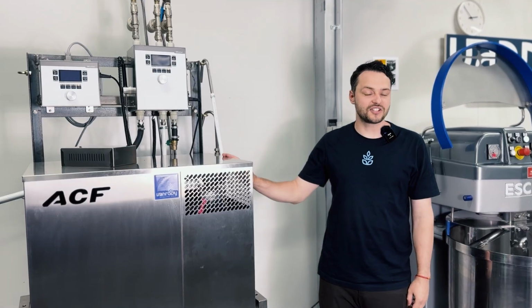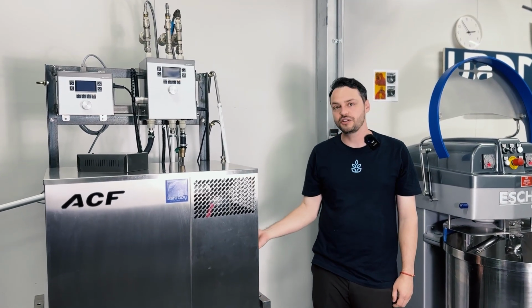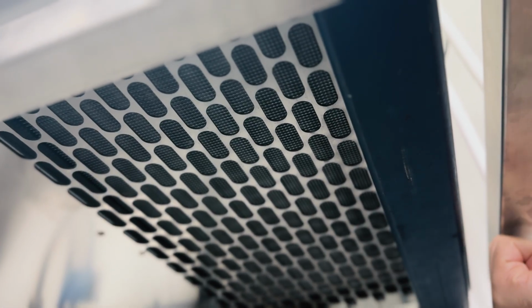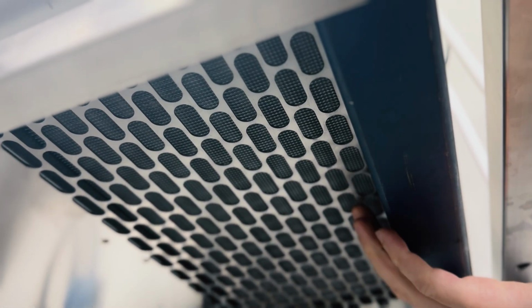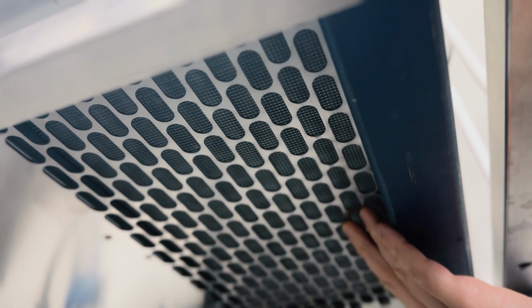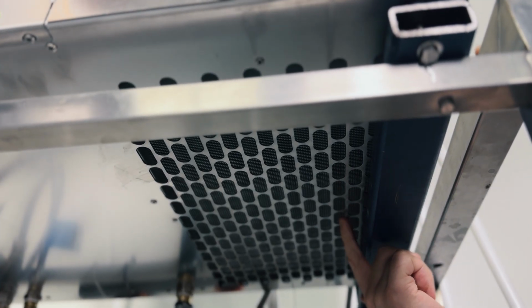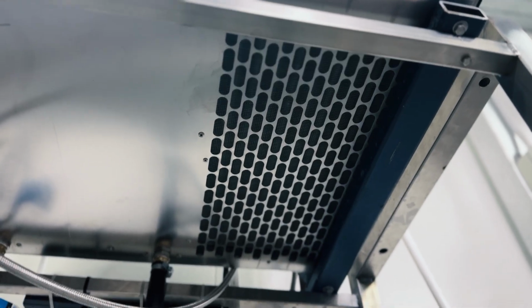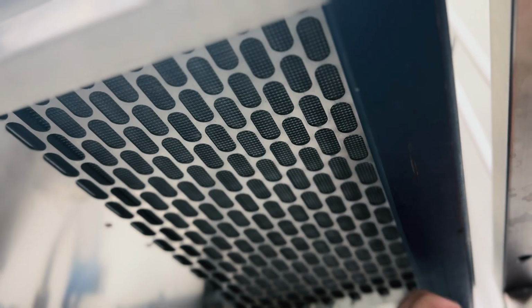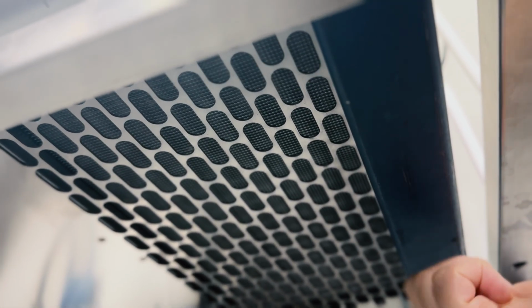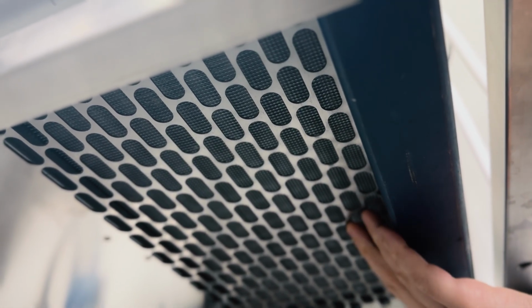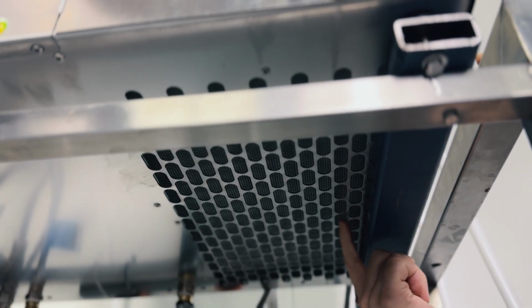So how often do we have to clean the fan? You need to check your fans monthly. Ideally, come underneath your machine here at the bottom, and you'll see some plating. There's a grill inside to protect our fingers and to protect the aluminium plates. Look inside past that, and you can see those plates. We want to make sure there's no flour buildup or dust buildup. If there is a lot of flour and dust, then it's time to clean it.